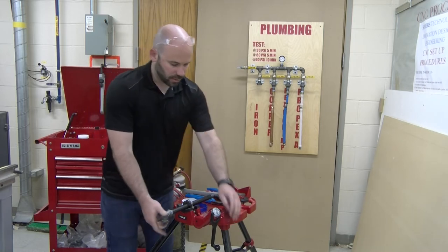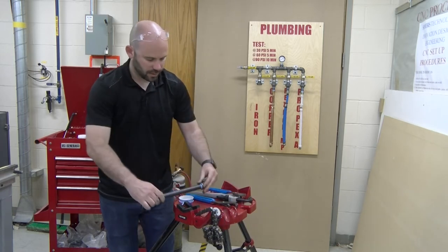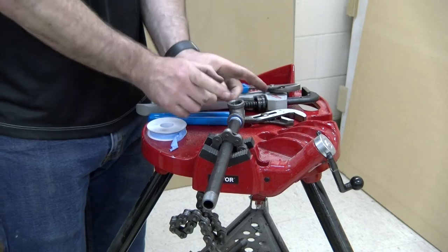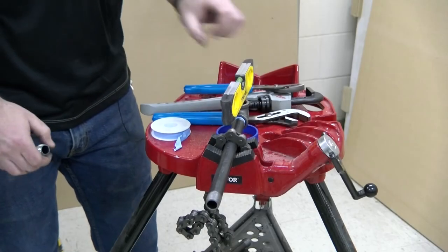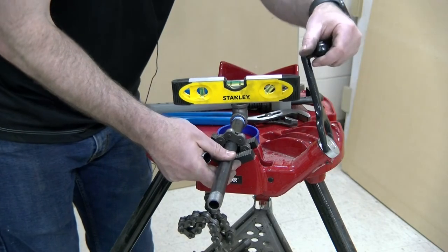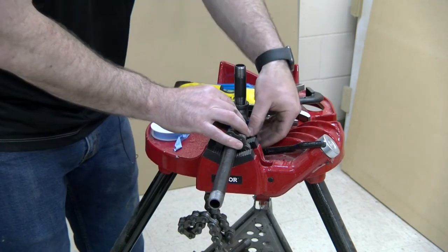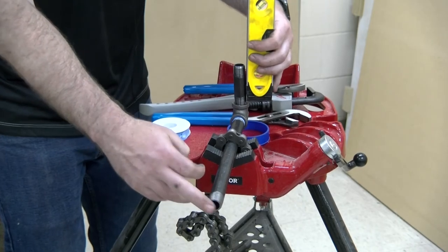Another thing to consider is position. When making these connections, you need to have the fitting plumb to something down the line. You would use a torpedo or pocket level to plumb this up — making sure the fitting is vertical — and then re-snug it down. Or you could apply what is called a riser pipe, a pipe running vertical, and apply a level to the face to make sure everything is plumb and the fittings correspond to each other.